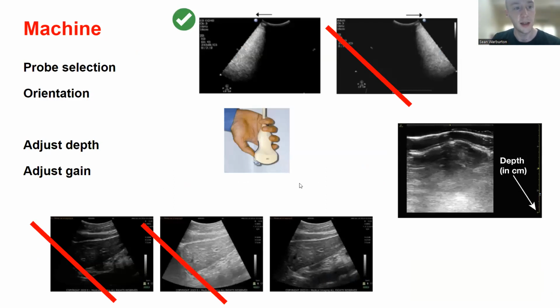Setting up the machine, there are 4 things you need to think about. The first one you pick up is making sure that you've got the right probe selected. If you pick up one of the probes and it's not selected on the screen, then it's not going to generate an image. You need to choose the correct probe, and we'll talk about that in a sec. Then you need to check if it's orientated correctly. So on the screen, you can see somebody's tapping the left side of the probe, and hopefully the left side of the screen flickers. But if the right side of the screen flickers, then you need to turn the probe over. Then you're going to adjust your depth and your gain.